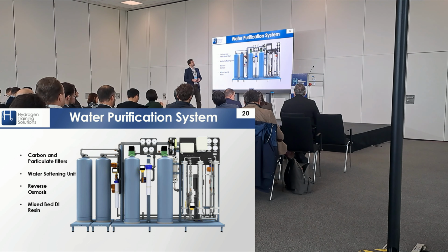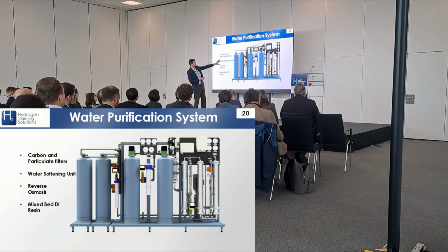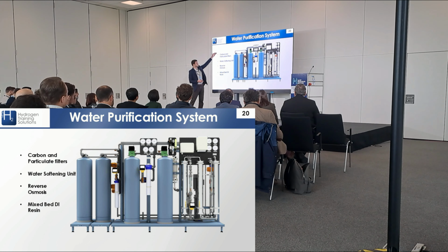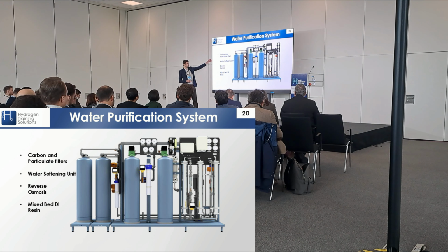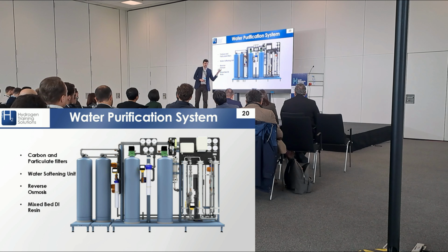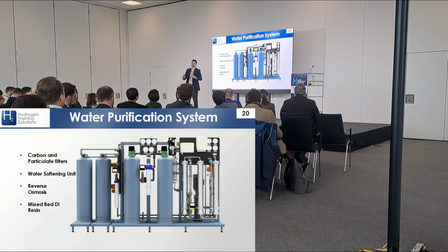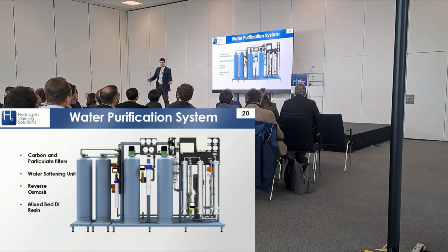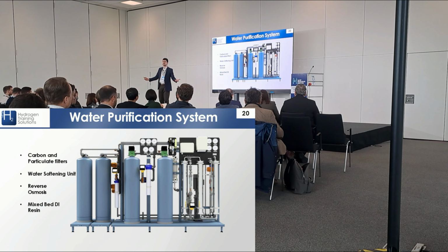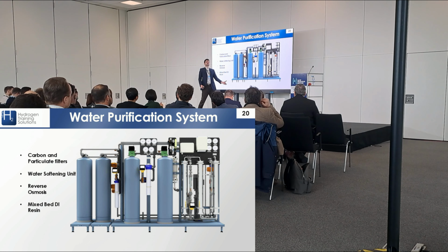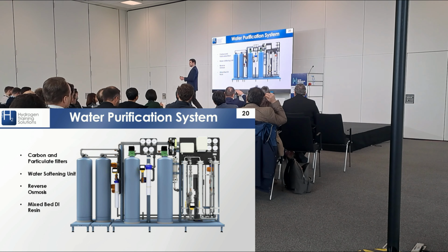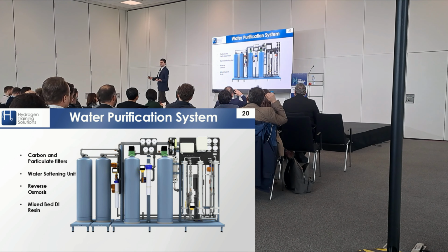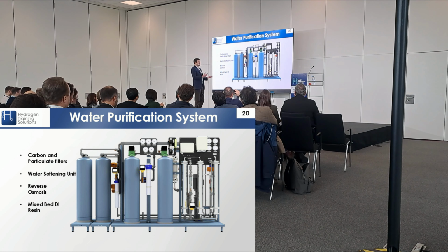We've got our water purification system on the left-hand side. Let's go through these: the carbon and particulate filters, the water softening unit, and the reverse osmosis. At the point going into the reverse osmosis, the water is about 600 microsiemens per centimeter. Downstream of the reverse osmosis filter, we get to around 10, 15, sometimes 20 microsiemens per centimeter with a really good reverse osmosis membrane.